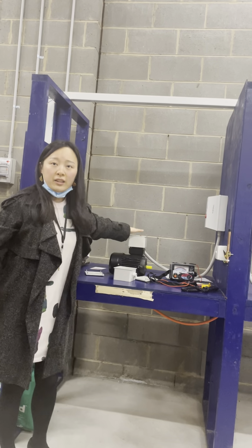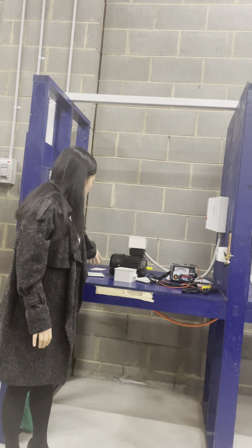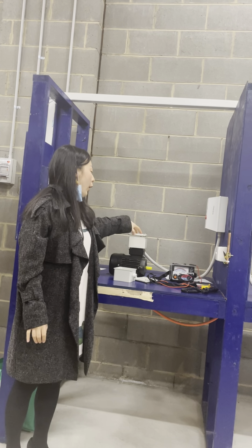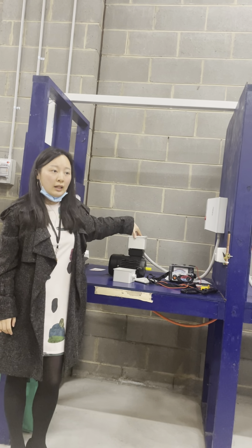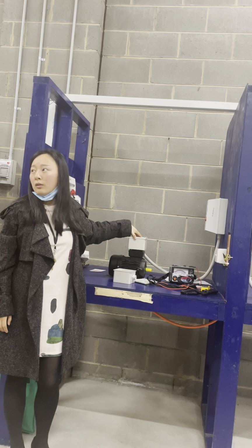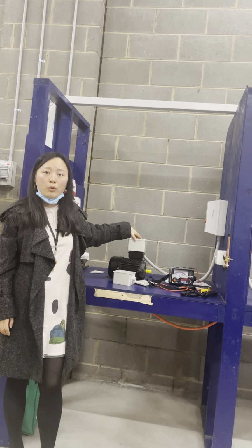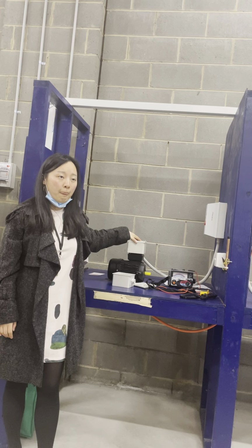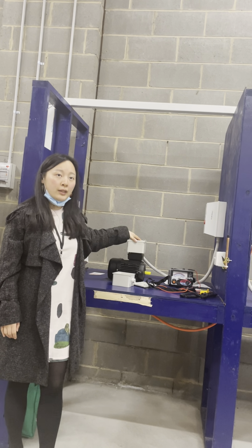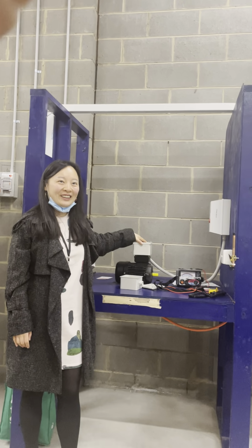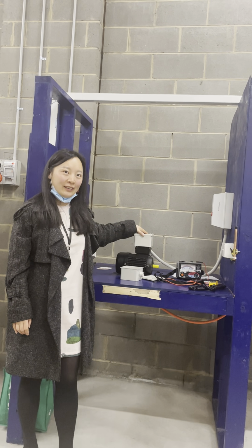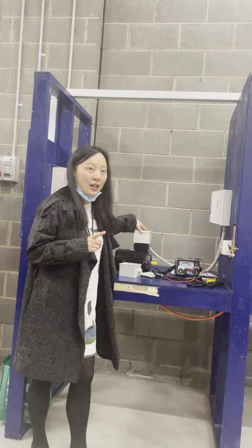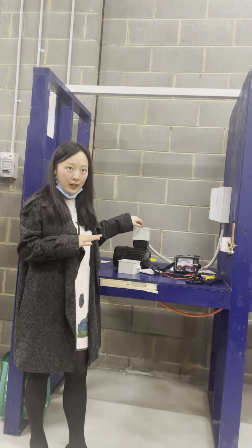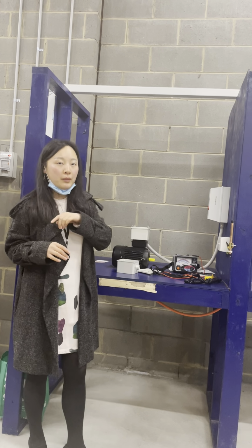Okay, so far I re-terminated all the cable. Am I supposed to do anything else before I go to the switchboard? Does anyone remember or know? Before I go to the switchboard, any more tests I need to do? No more tests? Yeah, there's one more test, earth continuity. Yeah, so now we terminated the cable, we need to make sure the whole earthing system is connected.